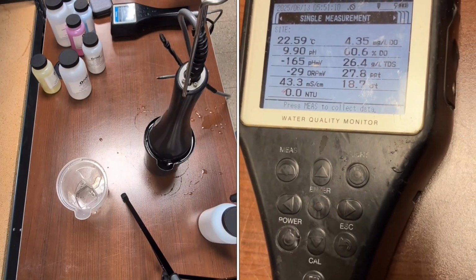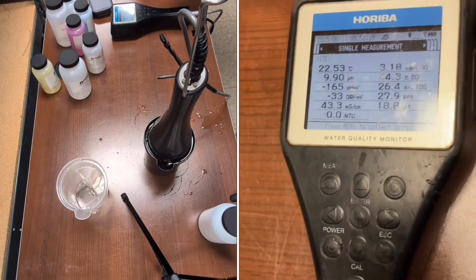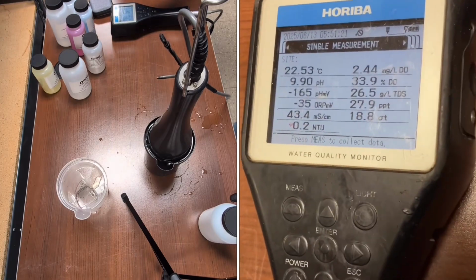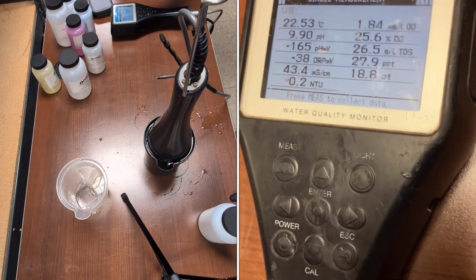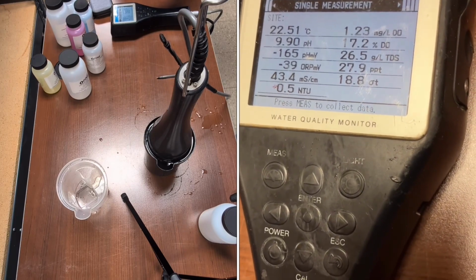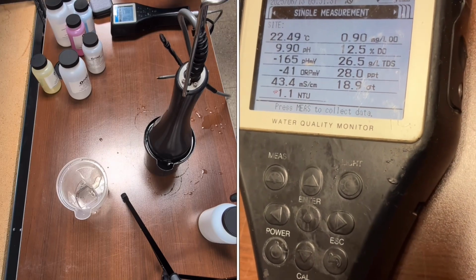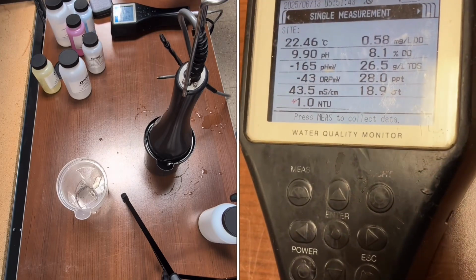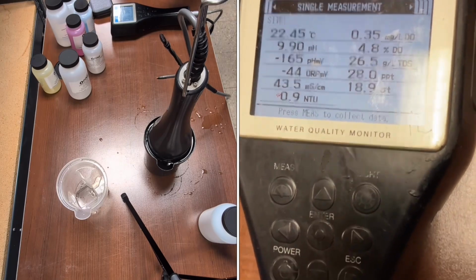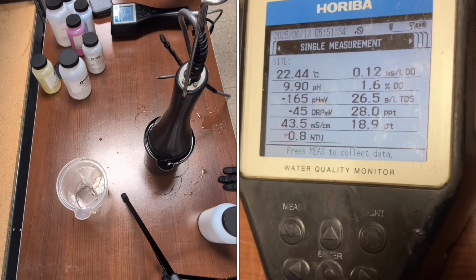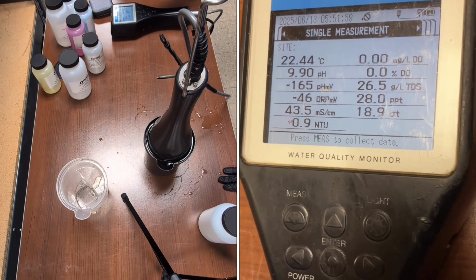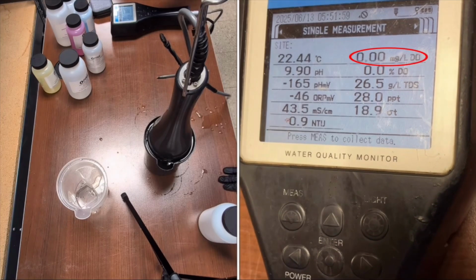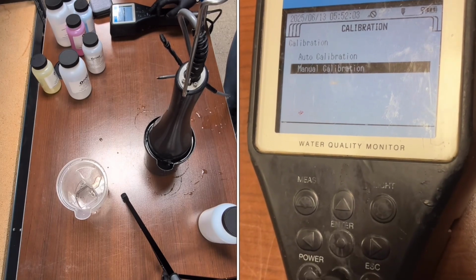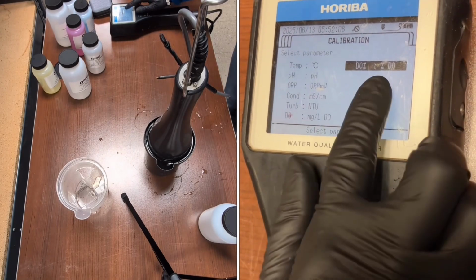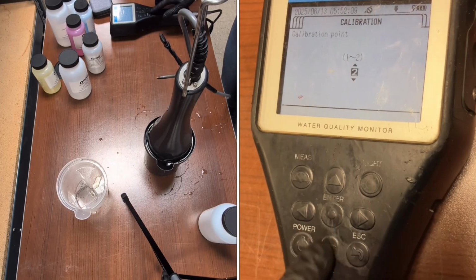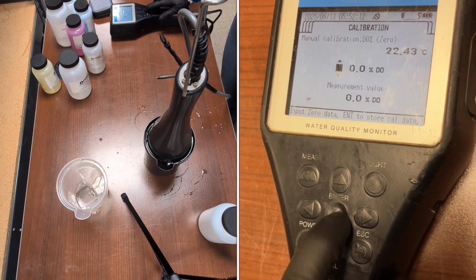And then from there, we're just going to wait for the mg/L and the percent DO to come down. I wait until the mg/L is below the threshold that we need it to be, which is 0.30. And once I see that the DO is below 0.30, I will write that number down. And then we'll hit the cal button, manual cal, and then we'll go to percent DO, and we will hit enter. It's a 2-point calibration, and we will calibrate to 0.0.